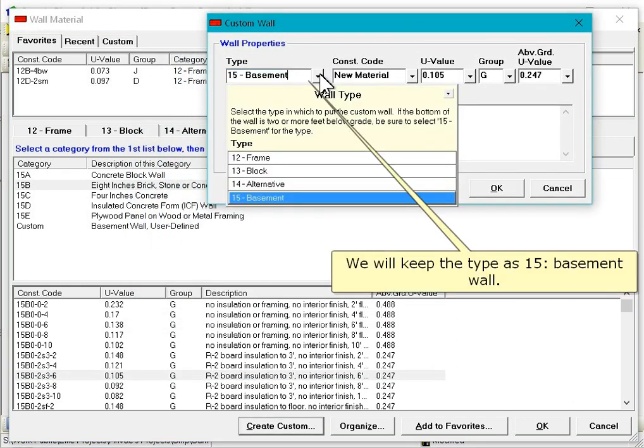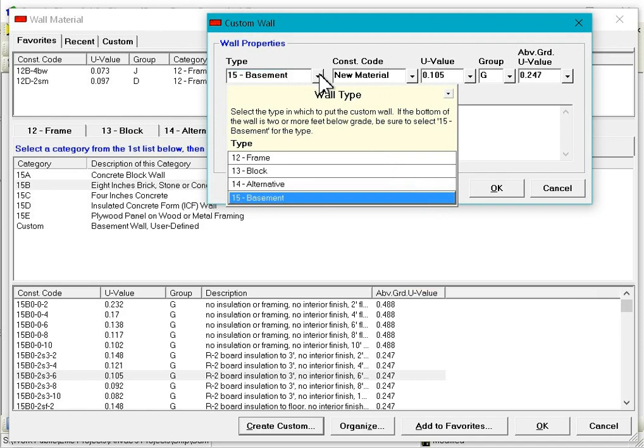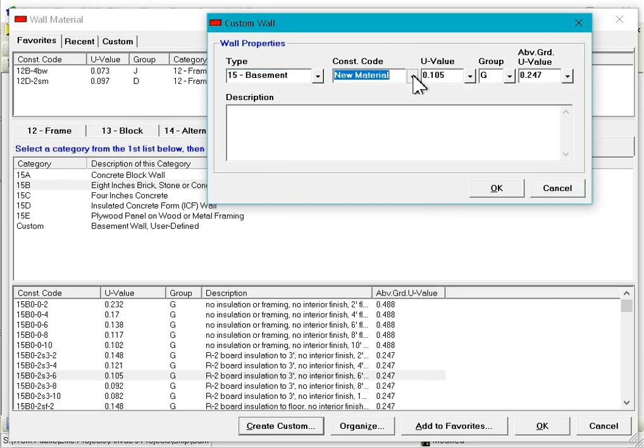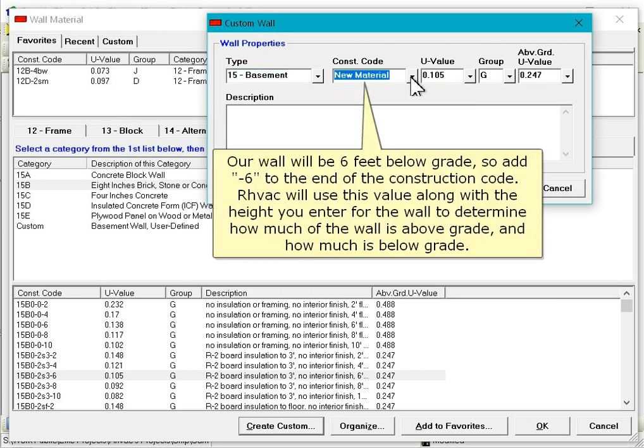We will keep the type as 15 basement wall. For a basement wall, the construction code must end with a dash followed by the number of feet below grade of the bottom of the wall. Our wall will be 6 feet below grade, so add dash 6 to the end of the construction code. RHVAC will use this value along with the height you enter for the wall to determine how much of the wall is above grade and how much is below grade.